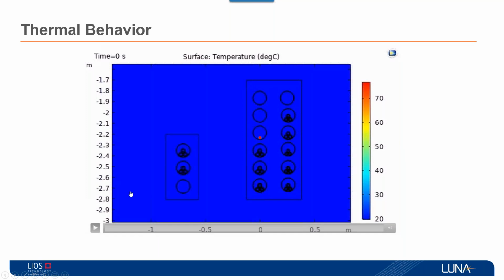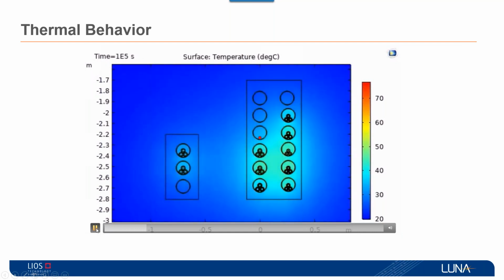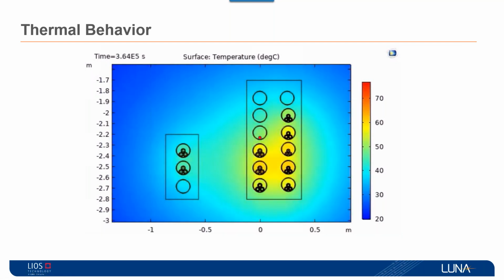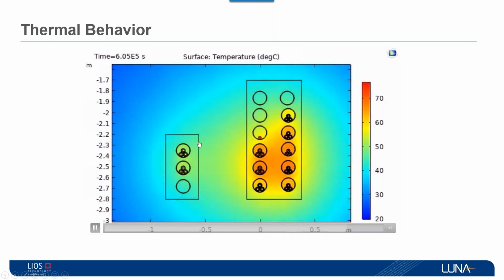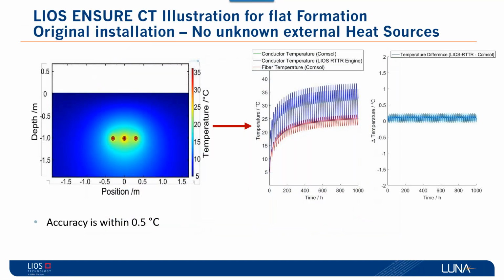Essentially, what we are interested in, before there is any steam pipe or not, is a congested duct bank that looks like this. Normally you have multiple circuits, and the fiber can be here. It's extremely challenging, but the exciting thing is that as the temperature is increasing, your fiber is also seeing the temperature, and you can interpret and extrapolate because we are modeling each thermal layer between the fiber and each of the circuits. We'll be able to know the temperature of the system. Not only the fiber optic temperature, but most importantly, each circuit will be able to be detected. Based on that, we give you an accuracy of how well the circuit will work, an accuracy of plus or minus 0.5, depending on how far you are from your cable.